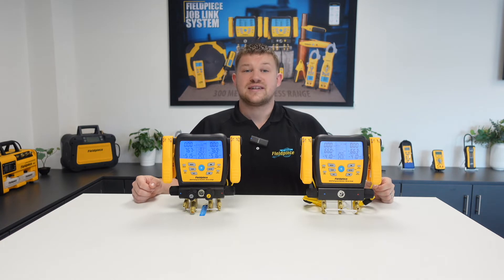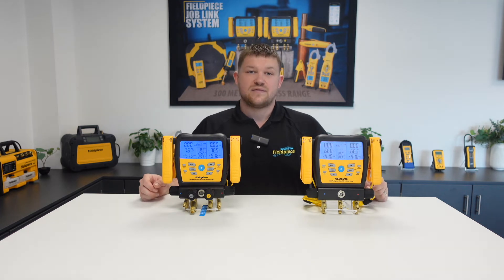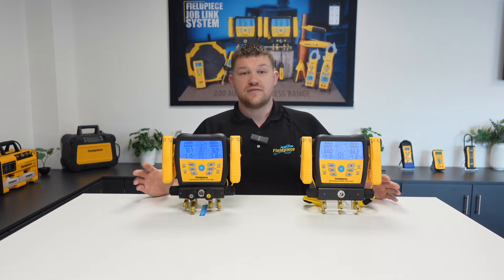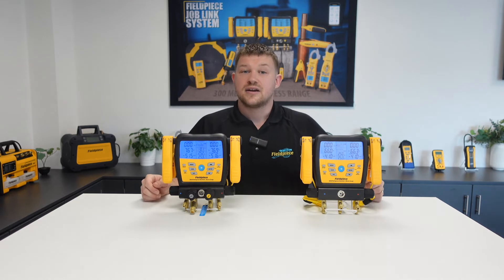Now before we start, I want to address that the Fieldpiece SM480 and the Fieldpiece SM380 manifolds have an integrated vacuum sensor. So why would you want to connect the MG44 to the screen when you already have a sensor inside the manifold block? The answer is that in order to take the best vacuum measurements on a refrigeration or air conditioning system, it's very important that you place the vacuum sensor as far away from the vacuum pump as possible.